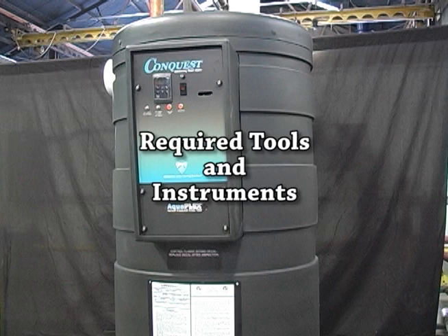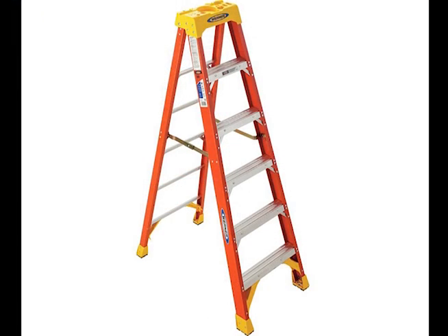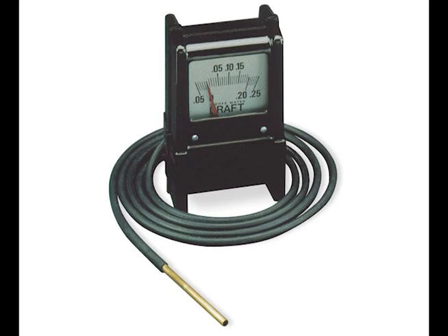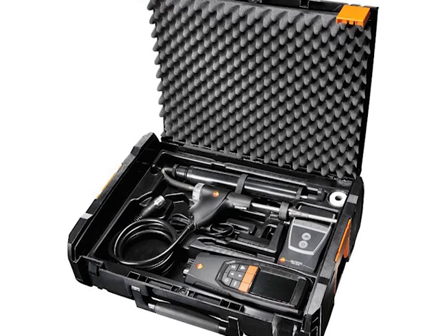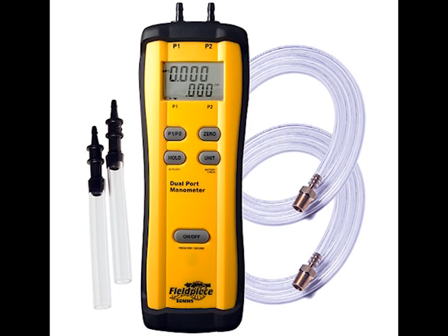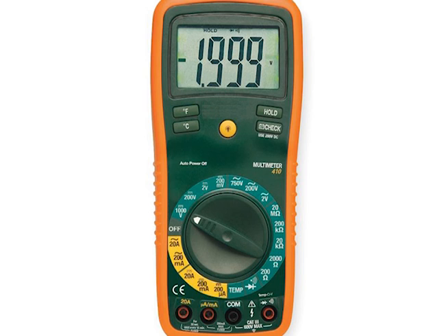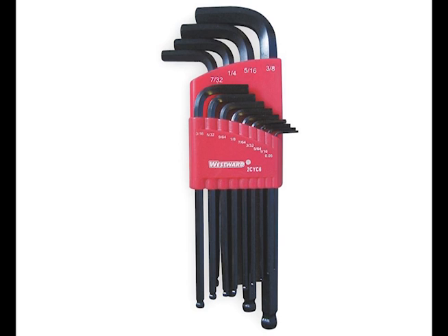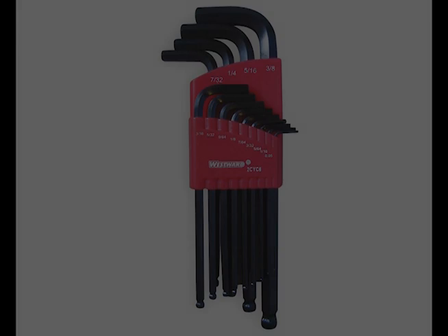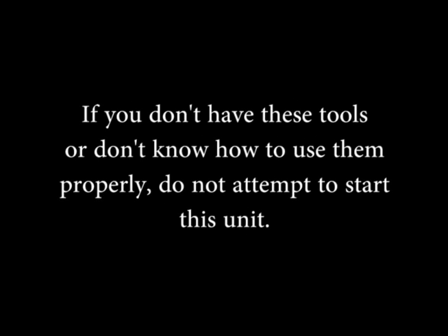The tools required for startup of the water heater are a 6-foot step ladder, stack draft gauge, electronic combustion analyzer, 2 U-tube manometers or gas pressure gauges, an AC/DC multimeter with 20,000 ohm per volt rating, and normal hand tools, including a 3/16 inch and 7/32 inch Allen wrench. If you don't have or don't know how to properly use these tools, do not attempt to start this water heater. Refer startup to a qualified technician.